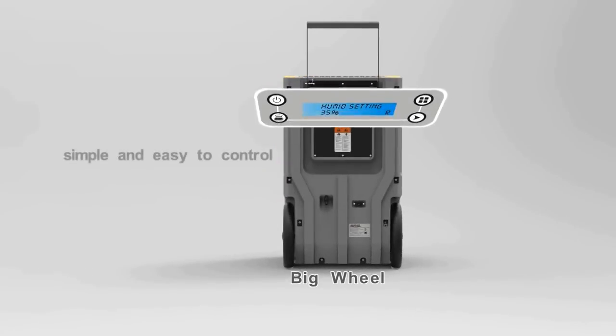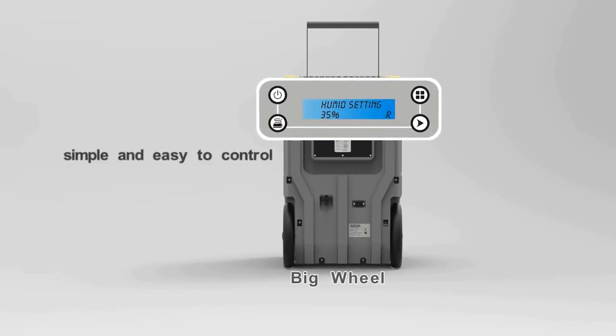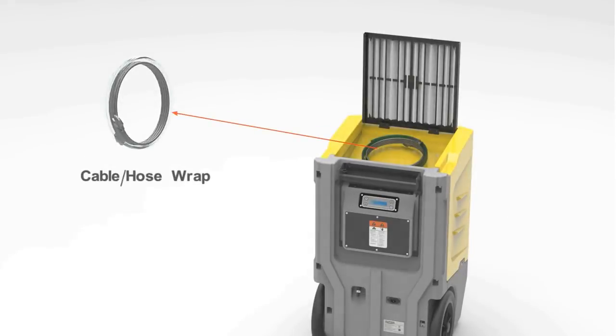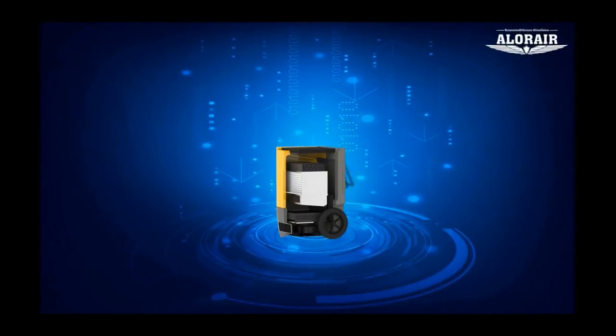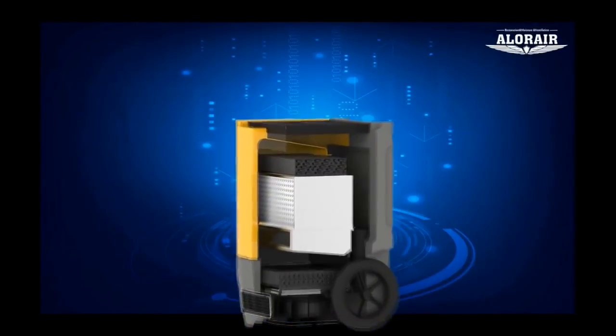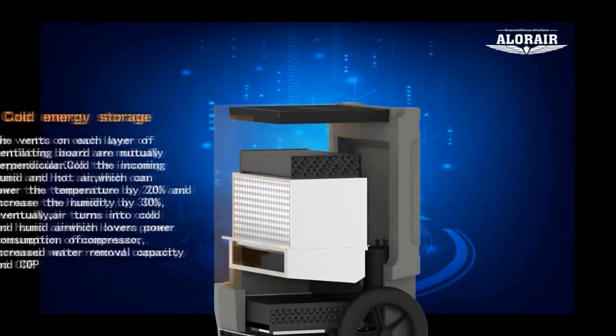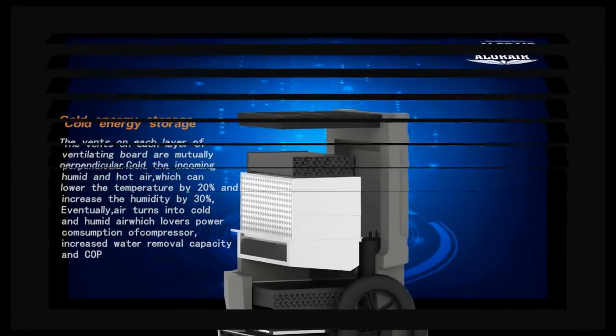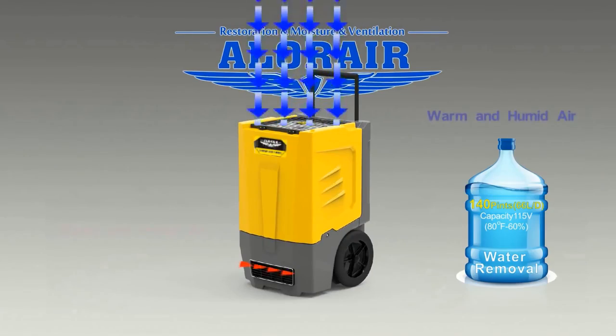It lowers the temperature of warm and humid air in advance by chilly condensate water from evaporator. As the main refrigerating medium, chilly condensate water lowers the air temperature beforehand, which reduces the compressor power, saves energy and increases humidity removal. Eventually, air passes through condenser and after that dry air discharges to the outside.